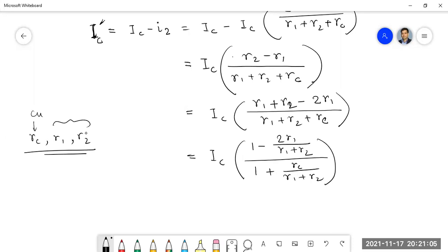Contact means the contact of carbon and copper. In later classes, I will discuss that a thin film of cupric oxide is formed at the interface of the carbon and hard drawn copper commutator segments, which increases the resistance. So generally, contact resistances are quite high compared to RC.